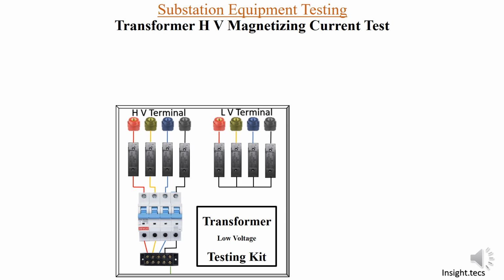For the transformer HV magnetizing current test, first we will provide earth, then neutral and three-phase supply. What we have to do is provide supply through the HV terminals, and keep the LV terminals open. The transformer HV magnetizing current test is also called the no load current test. So let us see how we have to make the various connections.